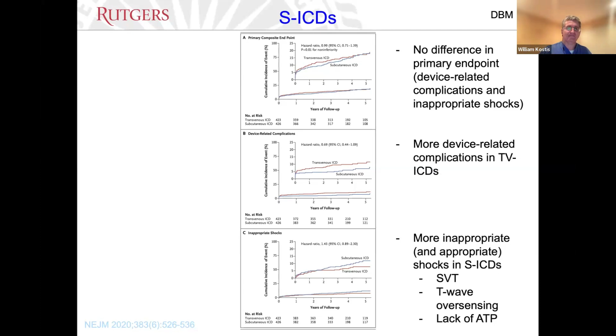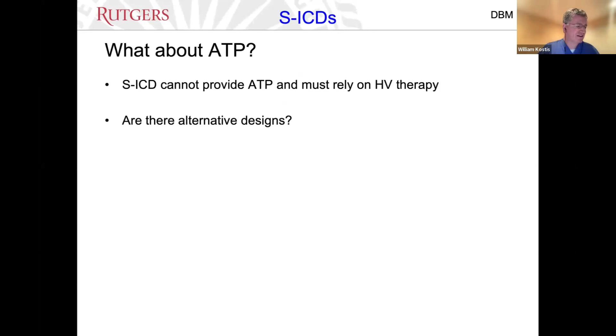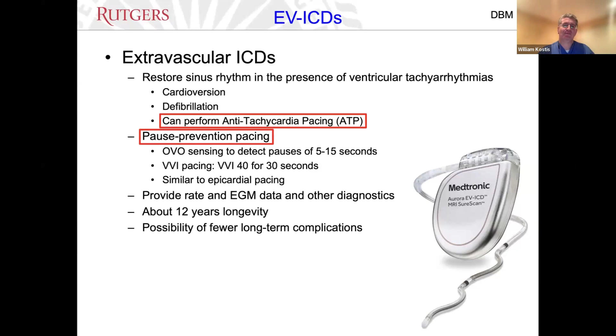So since you can't provide ATP with a sub-Q ICD and you can only rely on shock therapy or high voltage therapy, are there alternative designs that you can use? And the answer is yes. One of the companies recently came out with what they call an extravascular ICD. This is similar to a subcutaneous ICD with a pulse generator on the left lateral chest. Then, using a subxiphoid kind of mediastinal approach, you tunnel a lead into the anterior mediastinum near the heart. Because the lead is so close to the heart, and it's not just subcutaneous, it can actually perform antitachycardia pacing. In addition, for short periods of time, it can provide pacing to prevent asystole in what it calls pause prevention pacing, and that's selectable for pauses between 5 and 15 seconds.